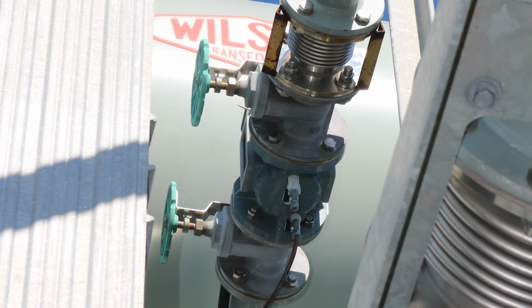There's a small sampling point at the bottom of the Buchholz relay, and in the event that we do have a surge, we can take a sample of the oil in that surge to work out what in fact caused the fault in the first place.